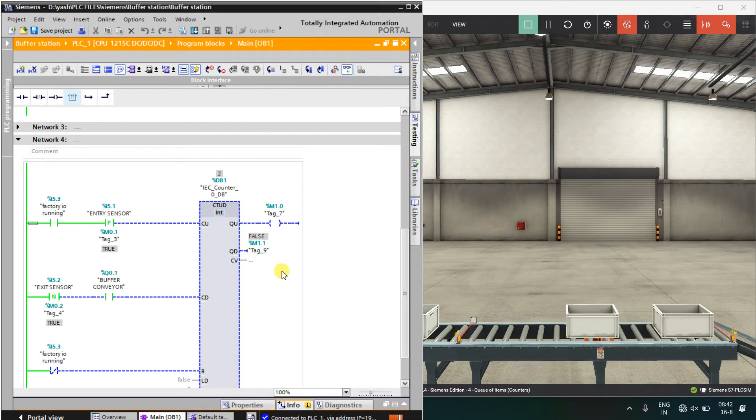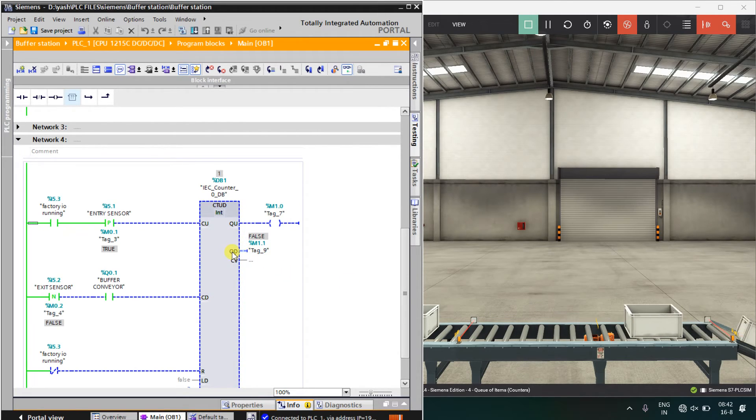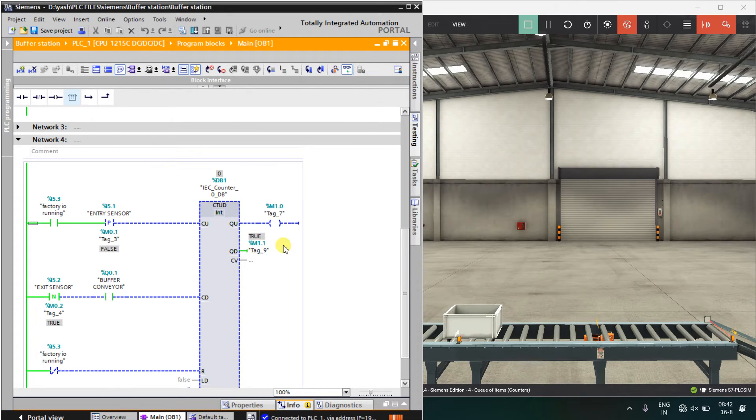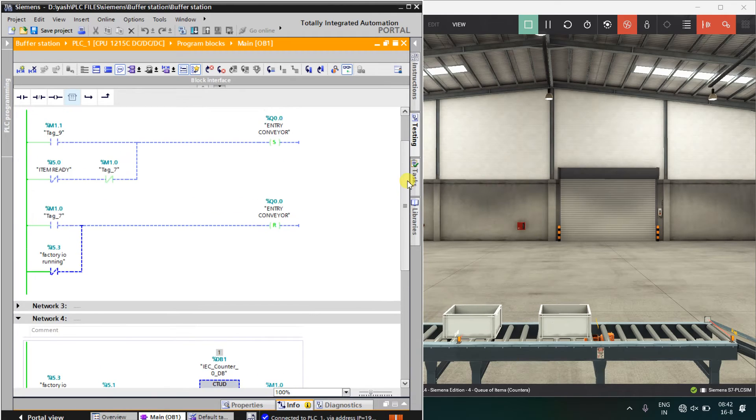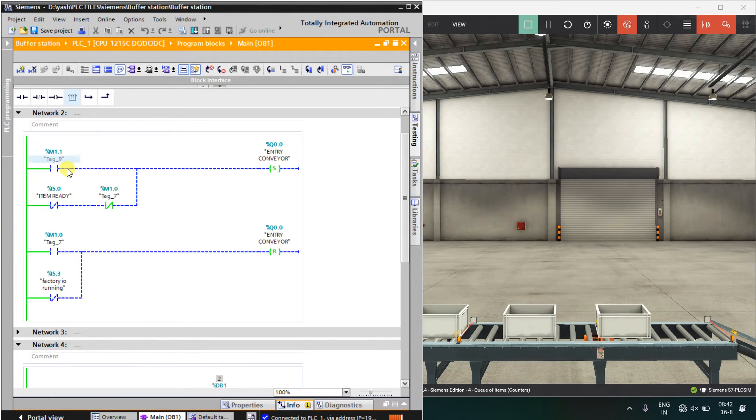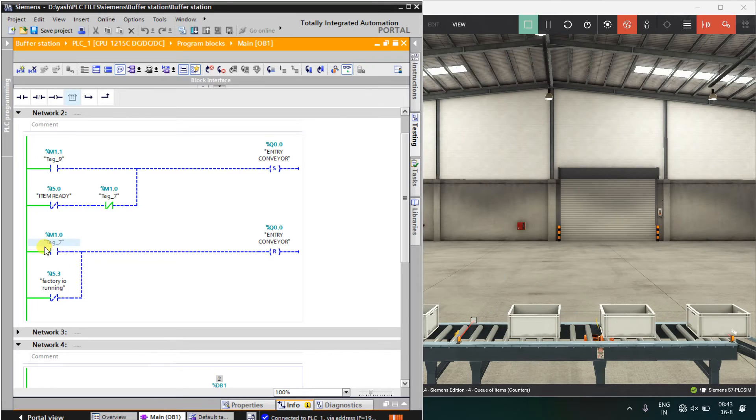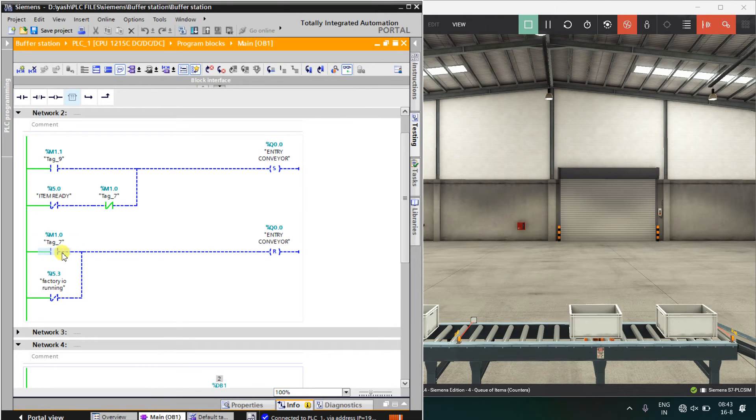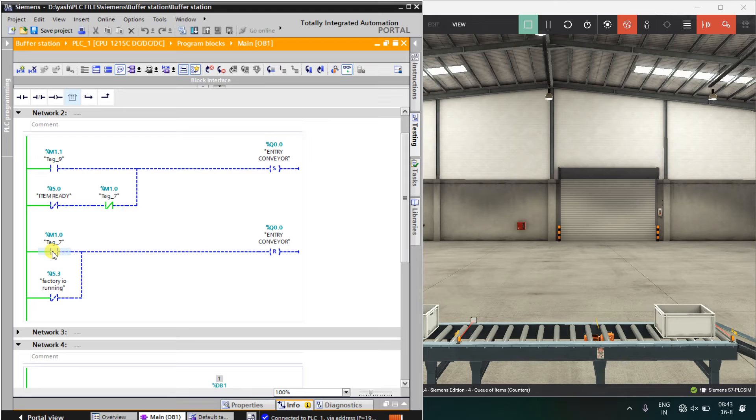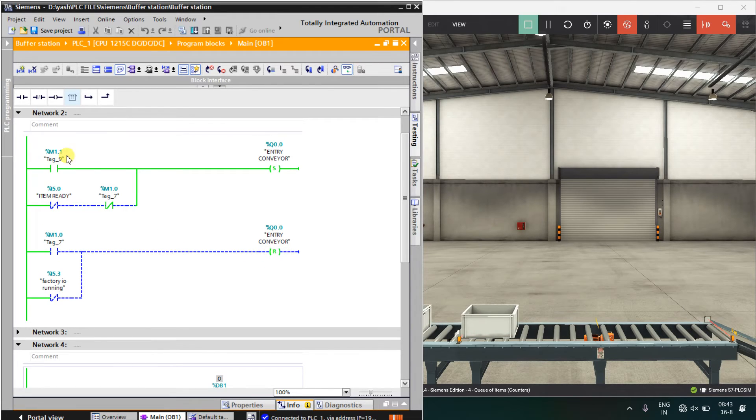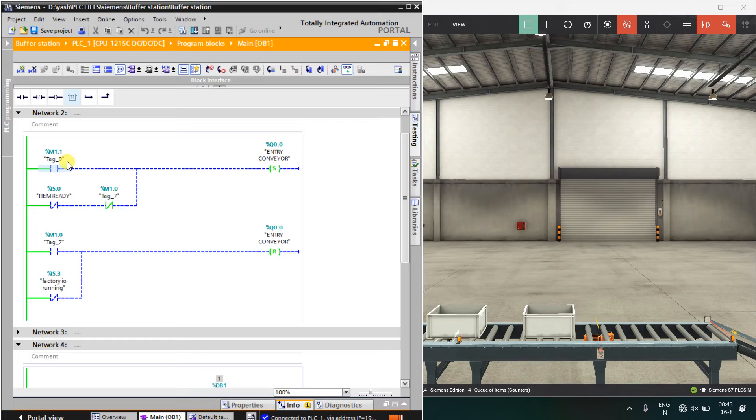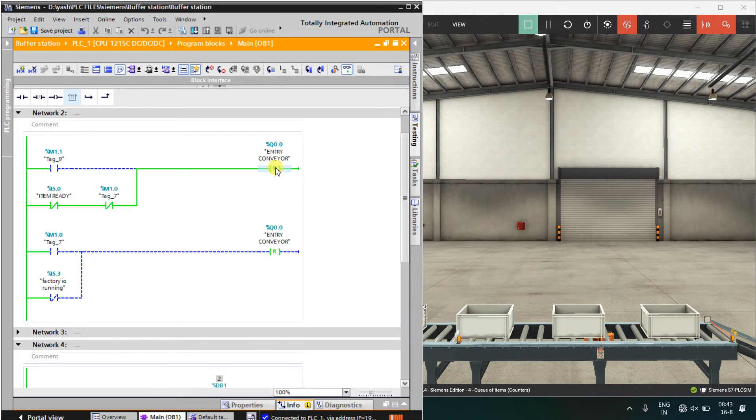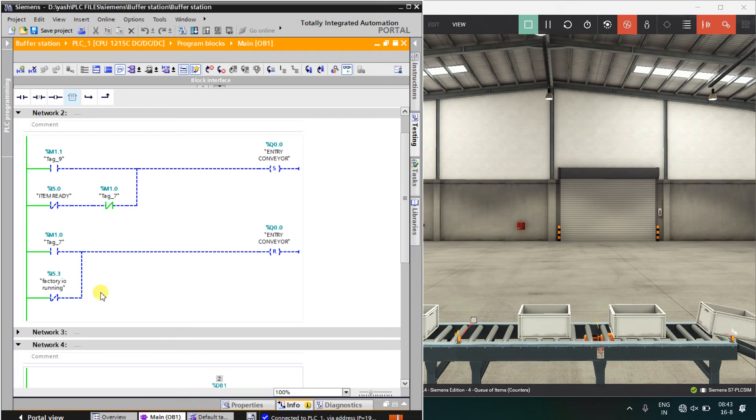When the countdown is completed, means three boxes have passed, M1.1 will be energized. M1.1 will again start the entry conveyor. Here you can simply see, when the count up is completed, means three boxes are on the conveyor, it will stop entry conveyor. And when three boxes leave the conveyor, this bit will be set and it will again set this entry conveyor.